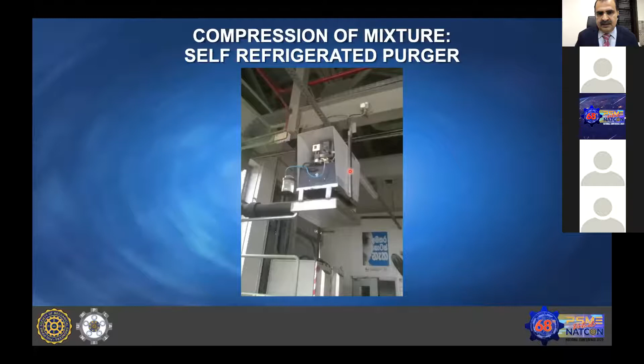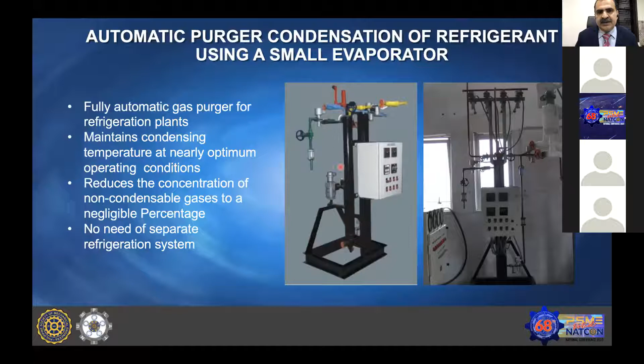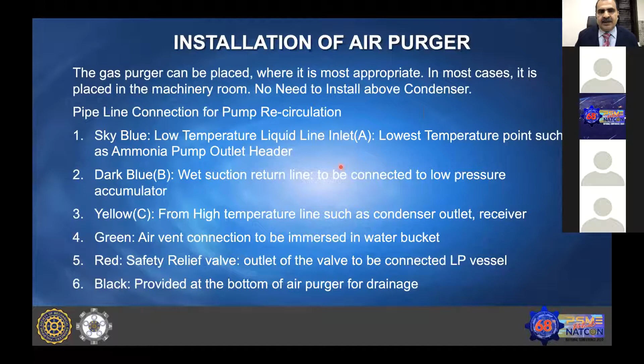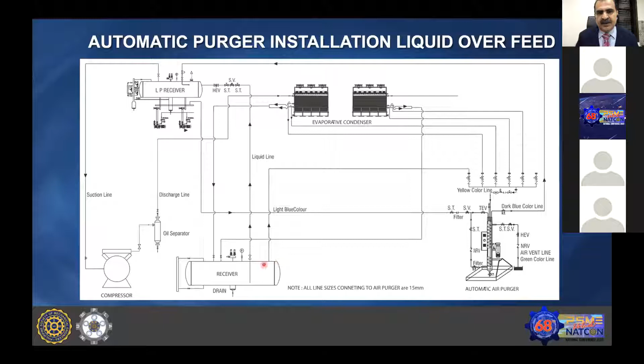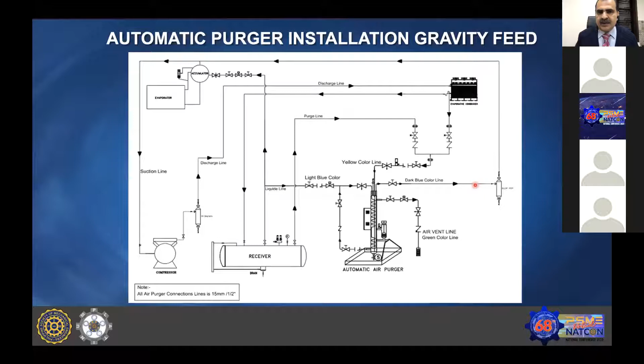This is a photograph of an actual purger, which has an inbuilt compressor system. And this is a photograph of an air purger which has a heat exchanger, which uses the inbuilt refrigeration system. The installations are very simple, normally because the purgers are available as well-built factory units. We need to provide a liquid feed line and a return line. And we have to take the purging points from different places like the condenser outlet or a receiver and connect them to the purger. We can install for gravity feed systems also.